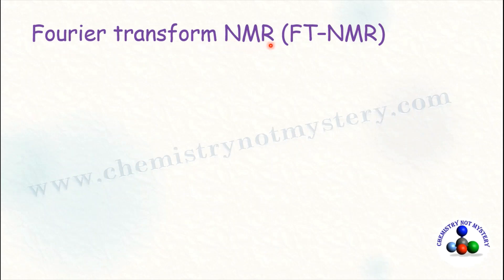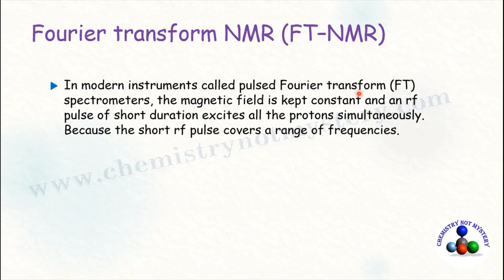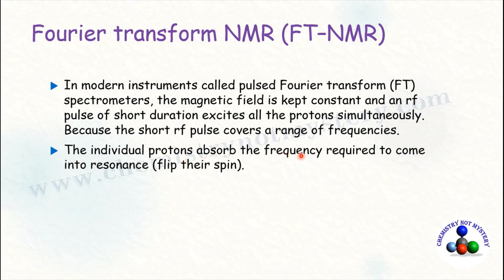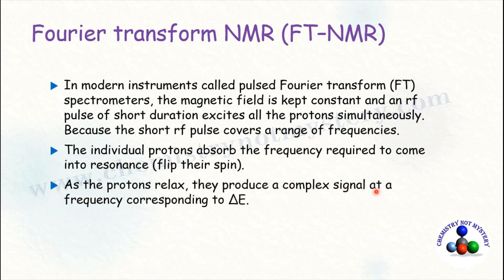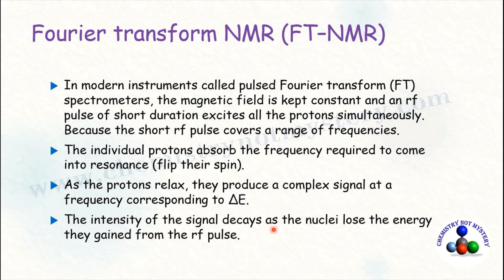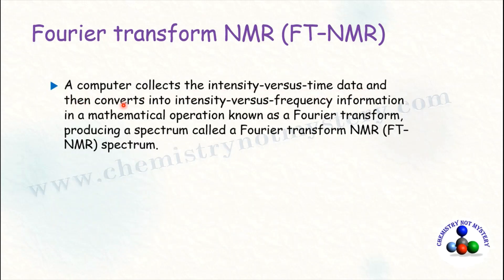In modern instruments called pulse Fourier transform spectrometers, the magnetic field is kept constant. A short radio frequency pulse excites all protons simultaneously because it covers a range of frequencies. Each proton absorbs the frequency required to flip its spin. As the protons relax, they produce complex signals whose intensity decays over time. A computer collects the intensity-versus-time data and converts it into intensity-versus-frequency information through a mathematical operation known as Fourier transform, producing the FTNMR spectrum.